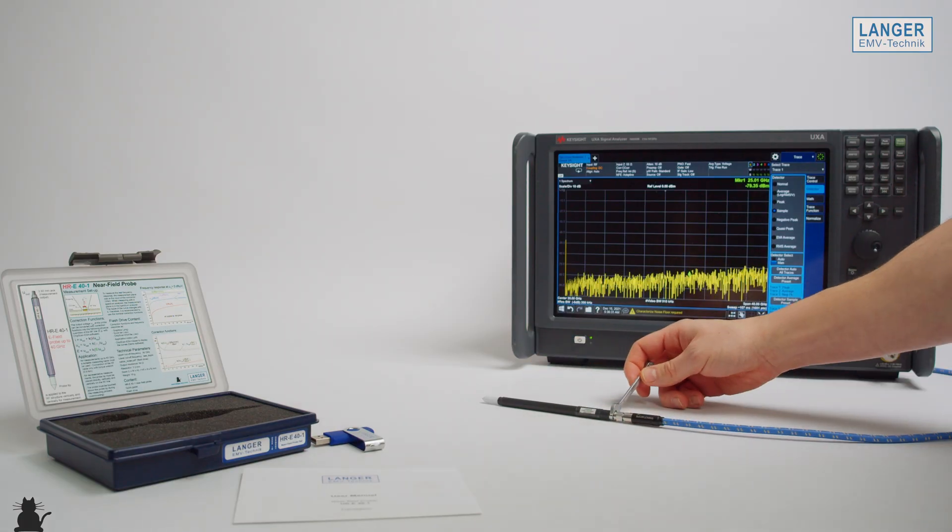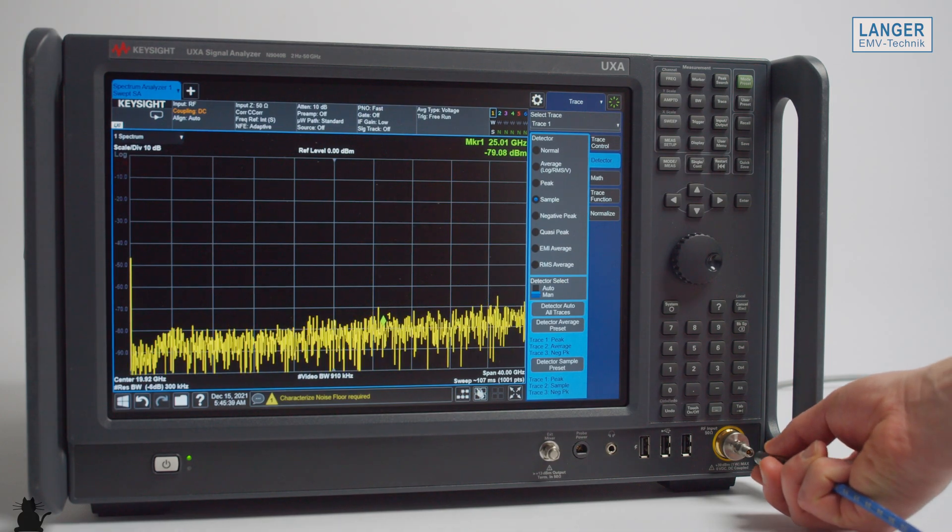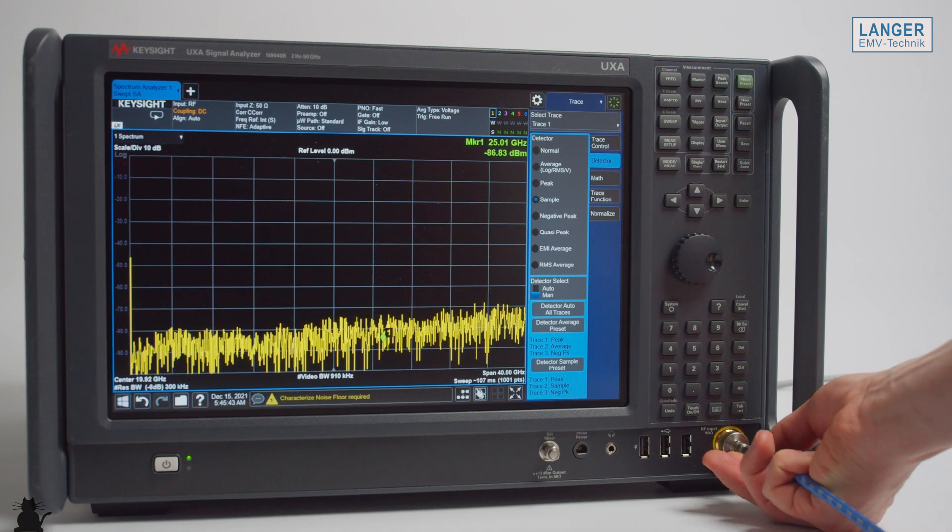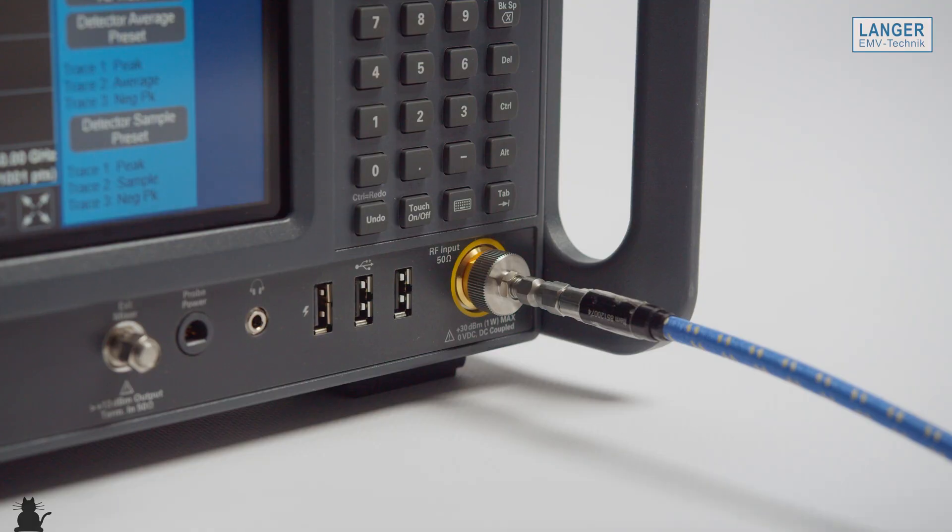The cable connected to the probe must be connected to the 50 Ohm input of a spectrum analyzer or network analyzer and also secured using a torque wrench.